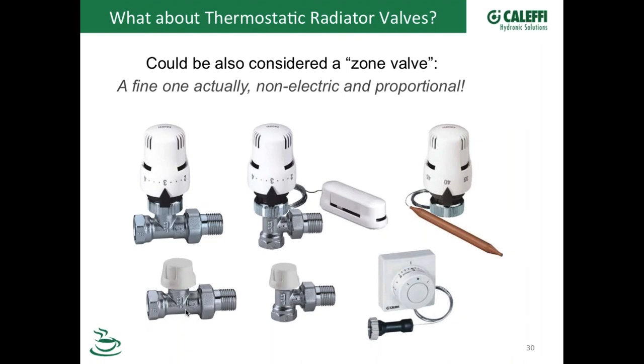And this is a very underutilized valve in the U.S. market. I just love this little valve, especially since I put a handful of them in my own house over the past couple years. Basically, it's a non-electric valve. So there's a little thermostatic cartridge in here, and it senses the temperature as the airflow moves through these little louvers, let's call them, on the side of it here, and then it opens and closes that valve. And not only does it open and close it to turn it on and off, but it modulates it.